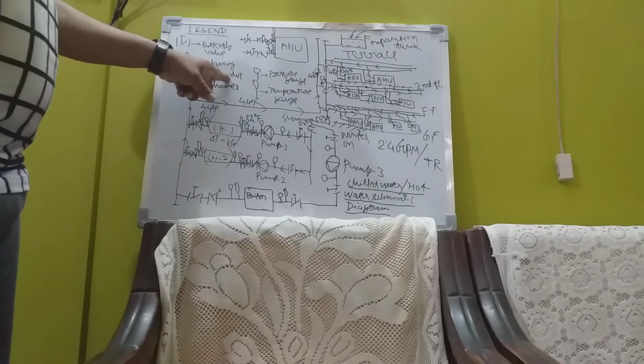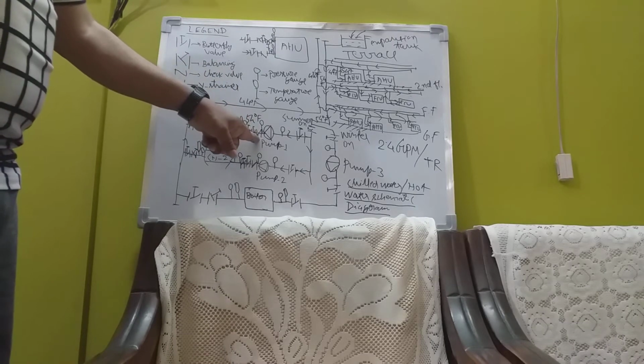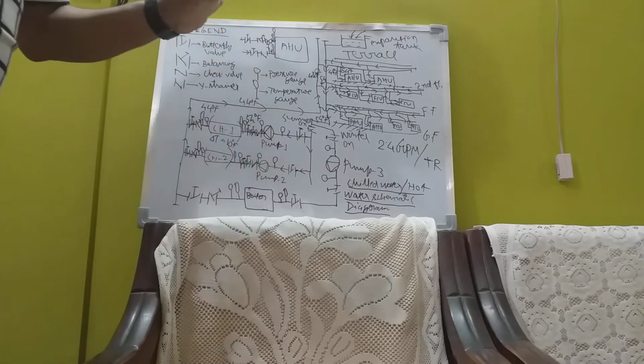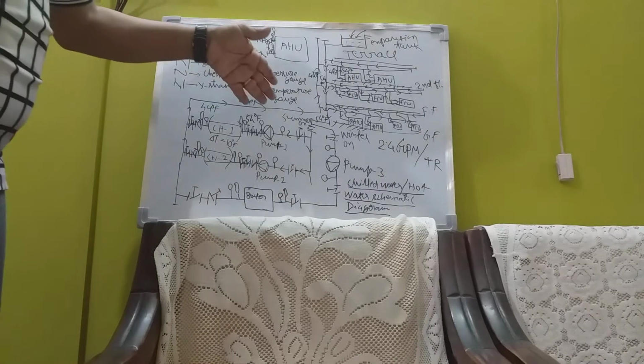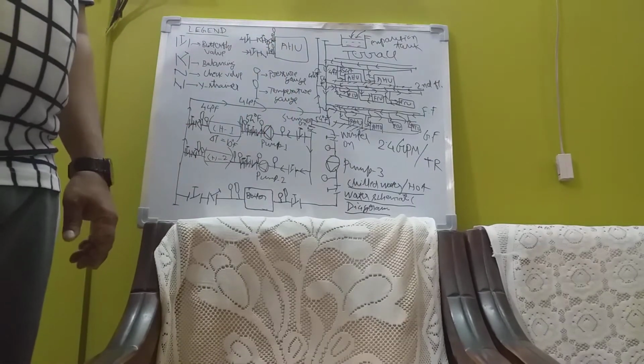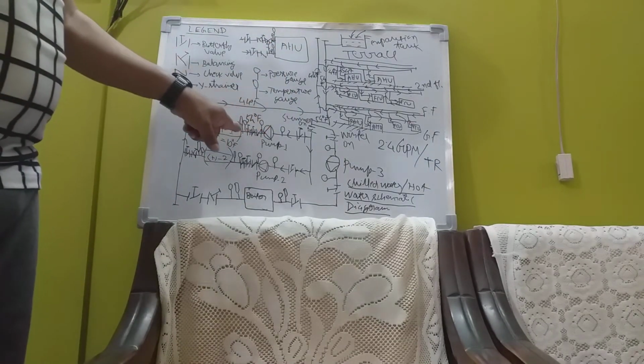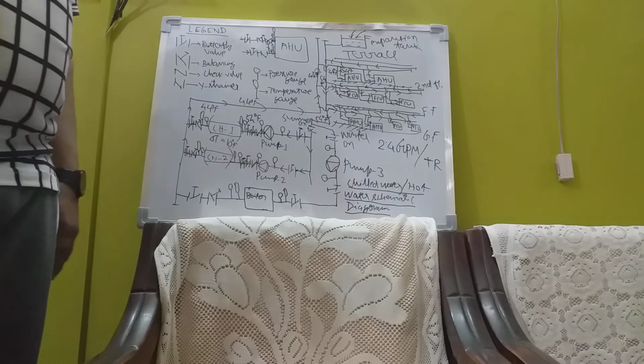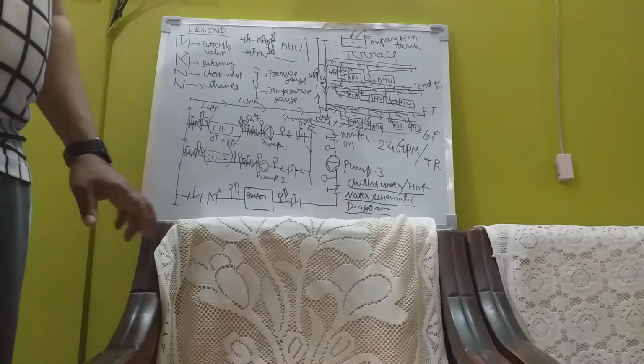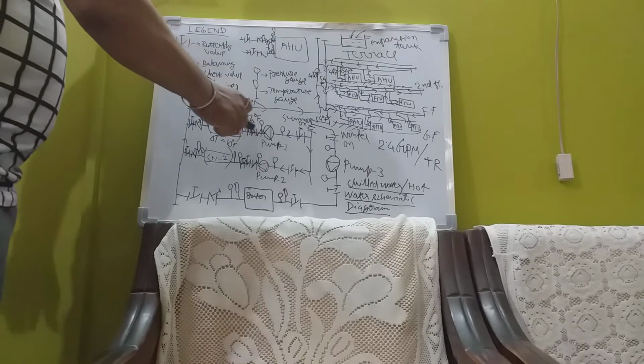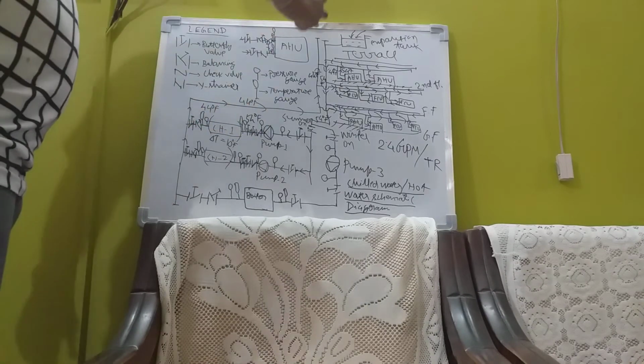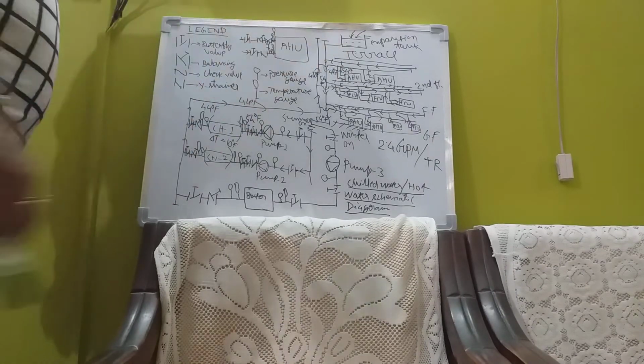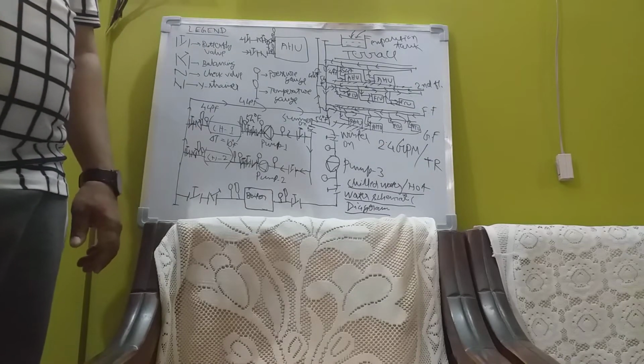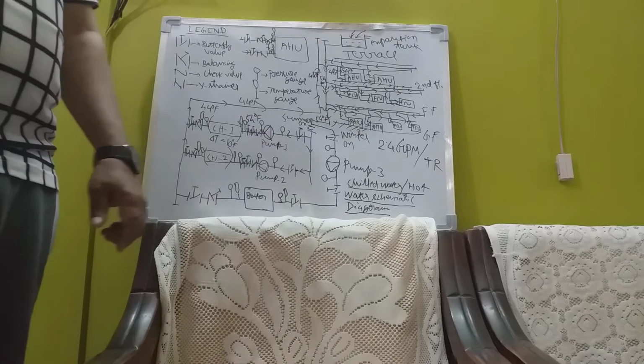Then we have the check valve. The check valve remains after the pump. The function of the check valve is not to allow water to come back to the pump. It's one-way direction. This way it goes, but it doesn't return that way. Why? Because the pump is pumping this much water to different heights. I am only showing here up to the second floor, but you may be supplying water to 80 floors, 90 floors in case of a multi-storey building.